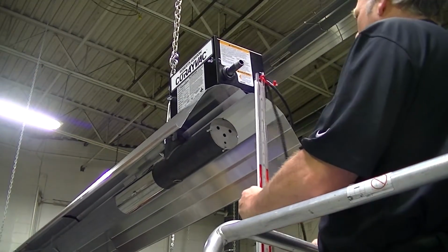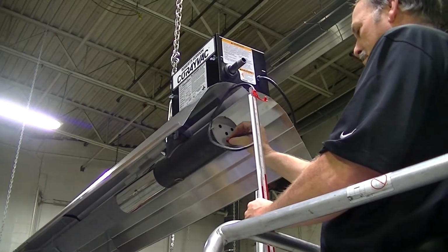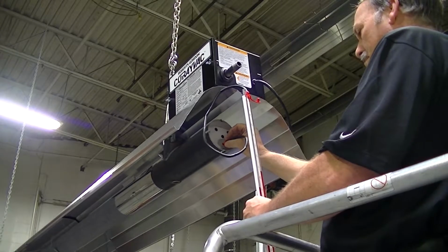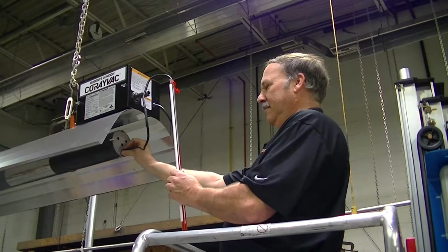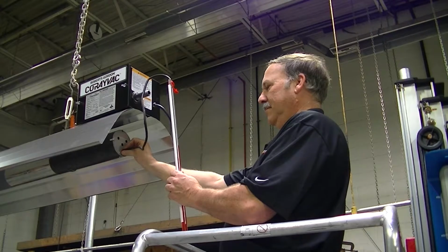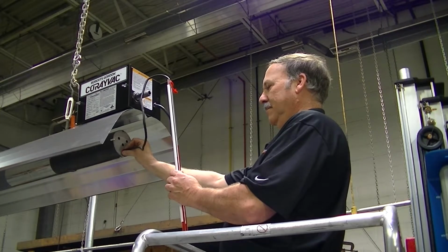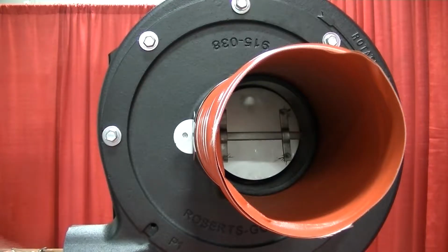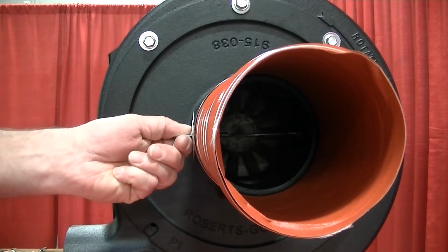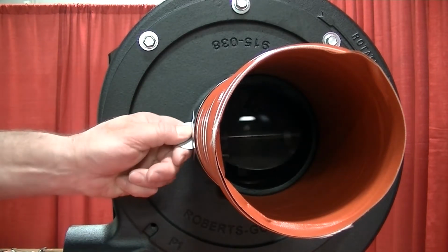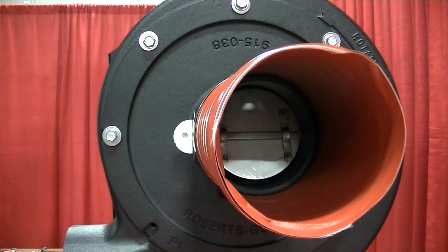Part of the commissioning is to ensure that the system vacuum is set properly. Vacuum should be 2.5-inch negative pressure after the system has operated for 20 to 25 minutes. To adjust the vacuum to negative 2.5-inch to 3-inch water column, adjust the damper on the inlet of the vacuum pump. Opening the damper increases the vacuum, and closing the damper decreases the vacuum.